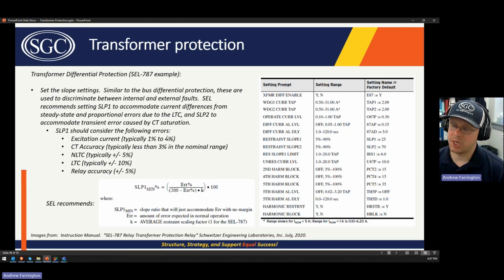Then we want to set the slope settings, and these are similar to what Brandon covered for bus differential relay protection. The first slope is used to account for proportional errors. So these are due to things like CT errors, excitation errors, and the load tap changer position. We know that we can change that to provide better voltage regulation through the transformer, right? And the LTC may be tapping all the time, maybe changing the turns ratio of the transformer several percent. So we want to account for that. So that's what that first slope is to account for.